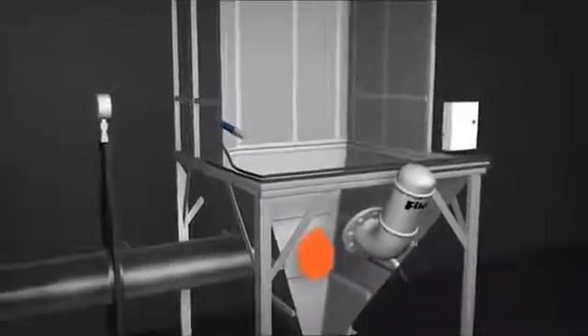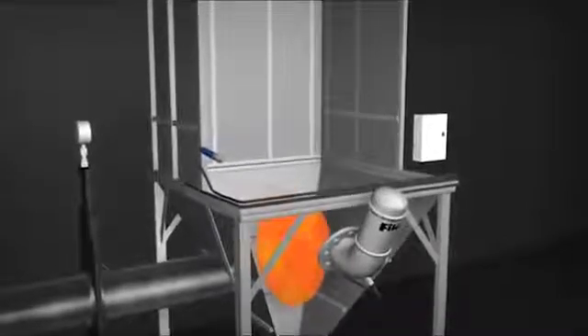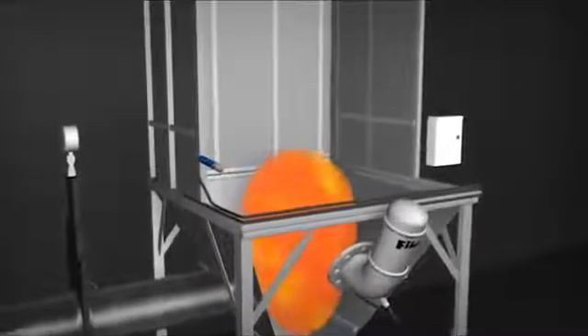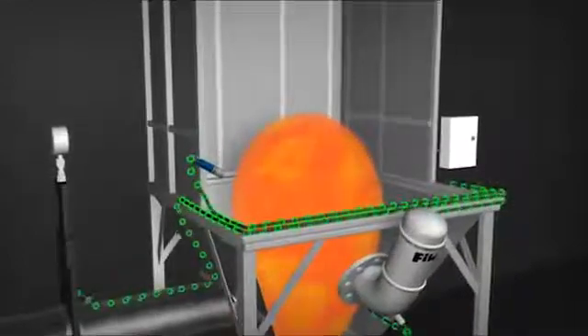The pressure front preceding the deflagration expands, reaching the pressure detector connected to the explosion protection control panel, which processes 4,000 data points per second.